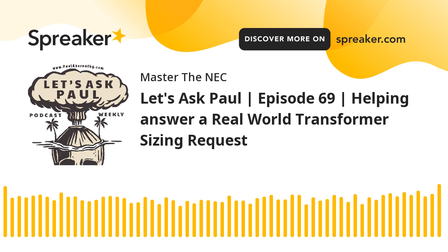Okay. So this makes sense. What you're doing here is you're saying, okay, I'm going to go from a 480 volt panel. This is your choice. And I'm going to go from a breaker, and I'm going to go out in a raceway. I'm going to go across the roof, an excessively long distance, and I'm going to hit a disconnect for the transformer. And then I'm going to feed that transformer, and then I'm going to come out on the secondary side, and I'm going to feed a disconnect for the HVAC unit. Okay? Sounds about what's taking place.